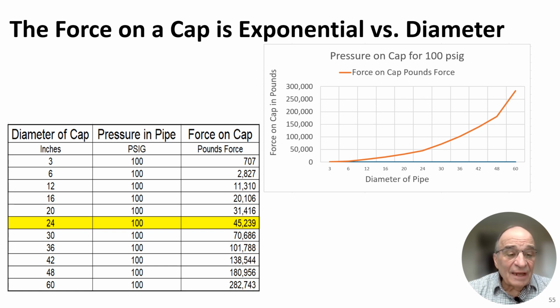The force on the cap, as shown here in a table form, and you can see the 12-inch main would be only 12,000 pounds, actually 11,300 pounds, whereas twice that size is not 22,000 pounds, but instead is 45,000 pounds. So knowledge of this is not something that was common knowledge on the job.